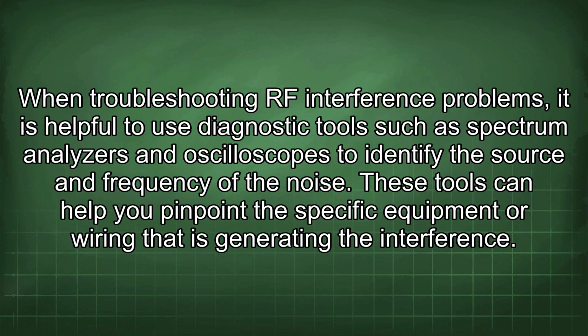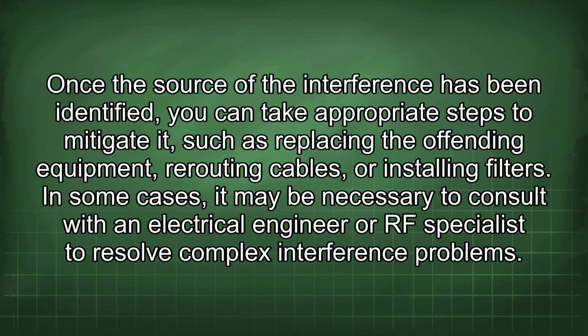When troubleshooting RF interference problems, it is helpful to use diagnostic tools such as spectrum analyzers and oscilloscopes to identify the source and frequency of the noise. These tools can help you pinpoint the specific equipment or wiring that is generating the interference. Once the source of the interference has been identified, you can take appropriate steps to mitigate it, such as replacing the offending equipment, rerouting cables, or installing filters.